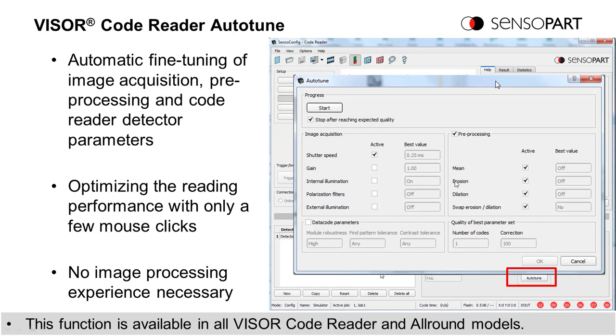So when you click Auto Tune, you get this dialog box. By default, you have pre-processing, and you're going to try these various filters. You could also vary the gain, and if you have external illumination, you could check internal and external illumination for it to try those options. If you have our polarizing filter, you could enable that. We have a polarizing filter where half of the internal lights are polarized and half are not.